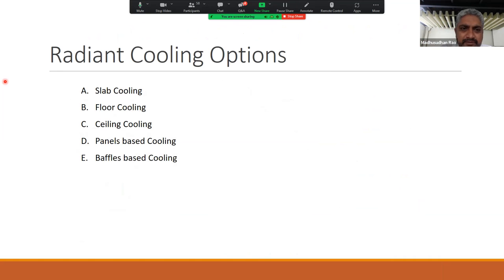Quickly, there are different ways it can be done. I'll show you an example for each of them. Slab cooling is what most people used to do in the early years of radiant cooling, where the pipes are embedded in the slab during the construction. The other is floor cooling, which is what we have been pushing most of the time, for multiple reasons. Ceiling-based cooling, where we can plaster the pipes on the ceiling. You can use radiant panels. Now we are also using baffles in some projects.